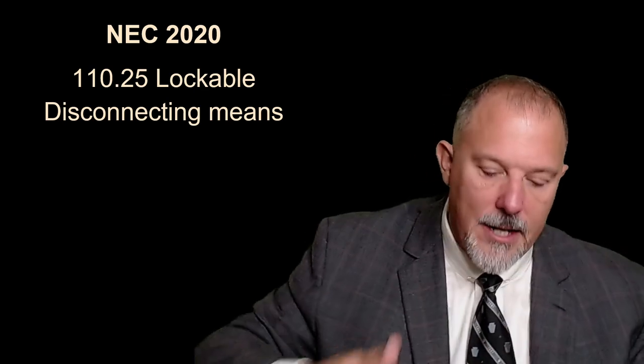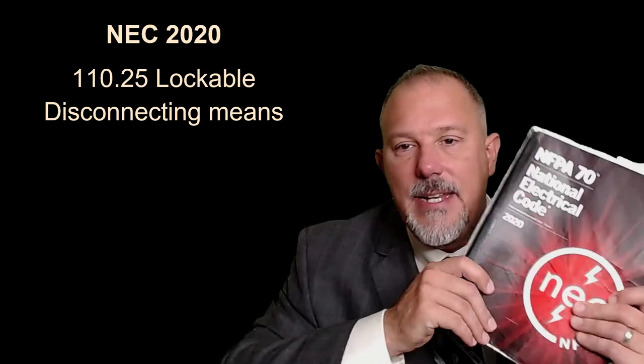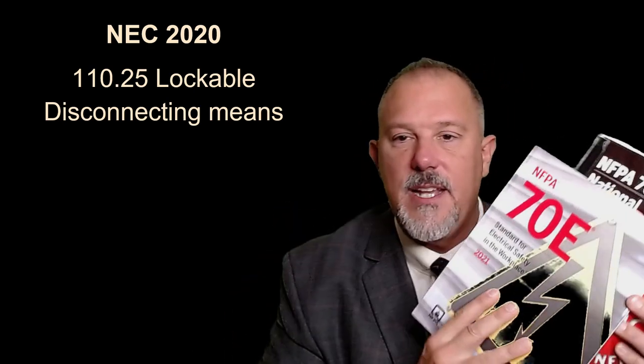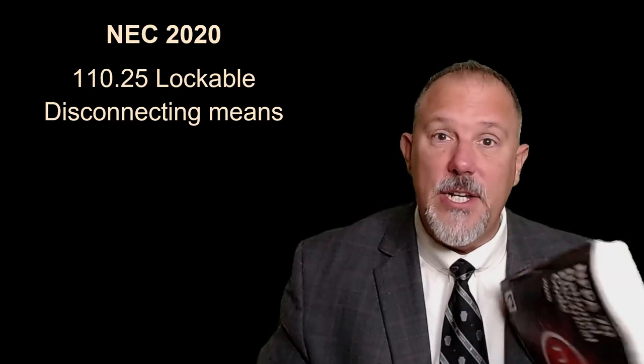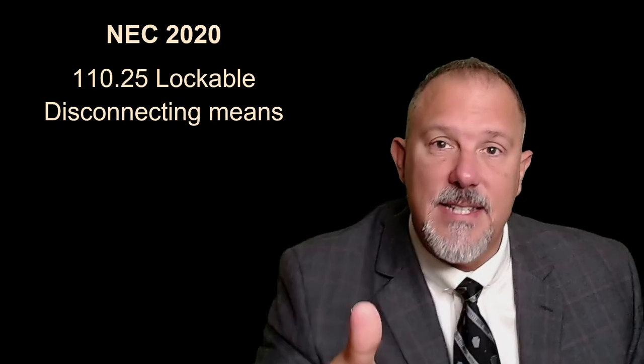So the National Electrical Code, you know, someone will say, how does the NEC work together with 70E? This is how we do it. And you can't forget 70B as well, which gets us right into our references. 29 CFR 1910. This is your general industry regulations. You need to understand these. You need to take a look at what the requirements are for things like lockout, tagout, establishing an electrically safe work condition, understanding the hazards.